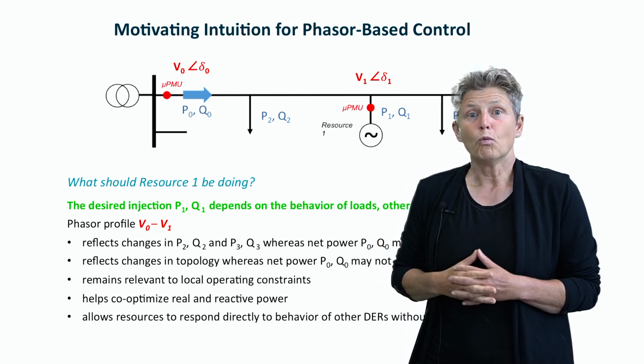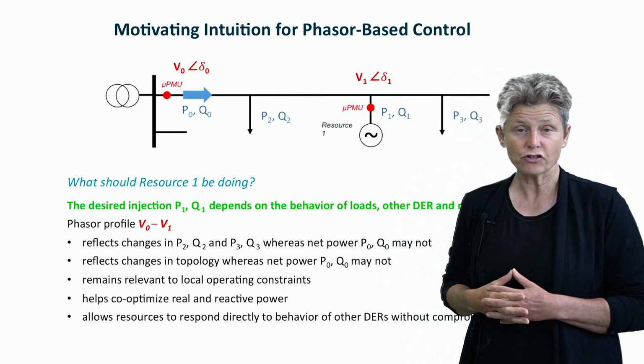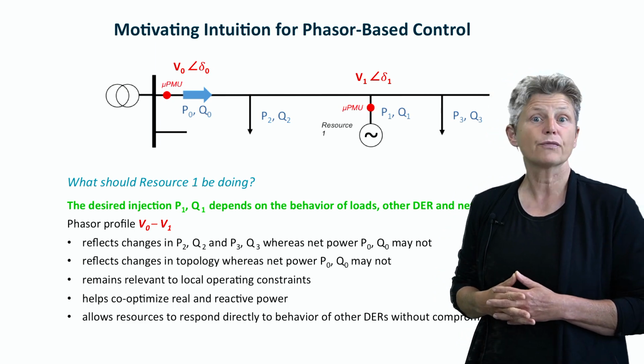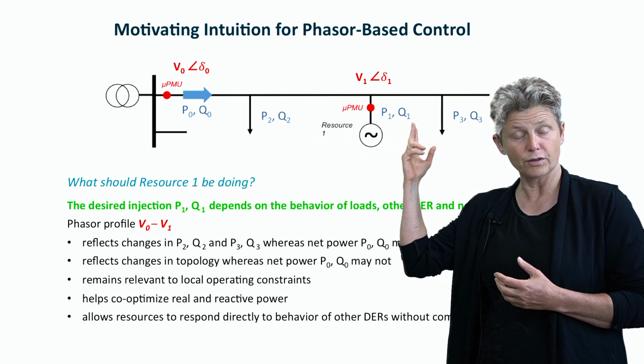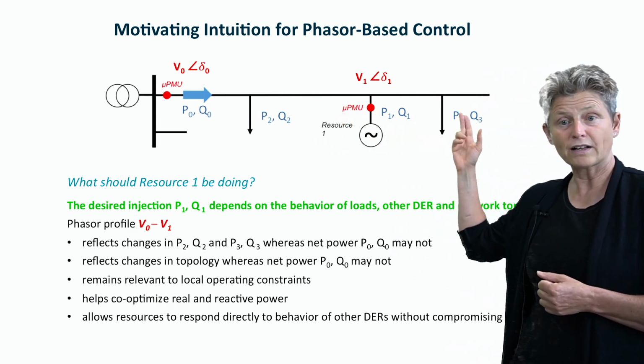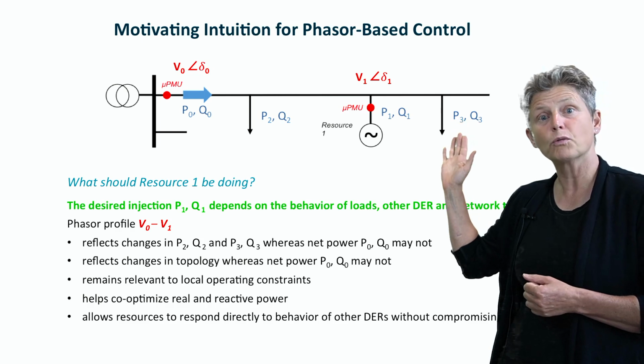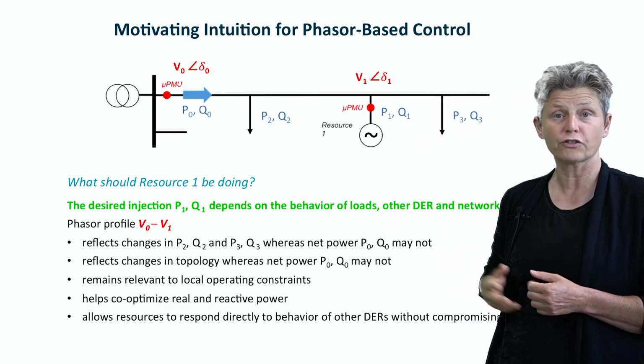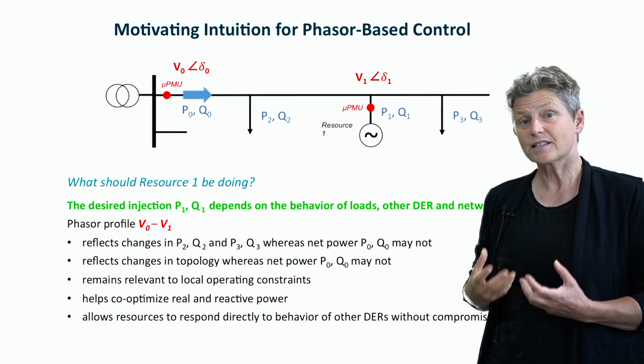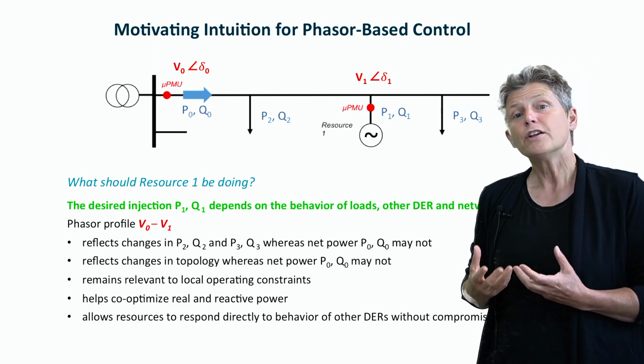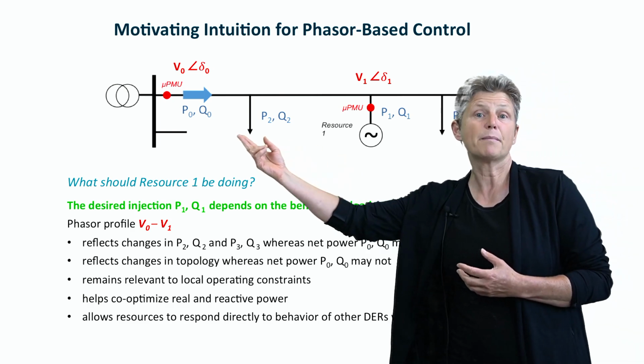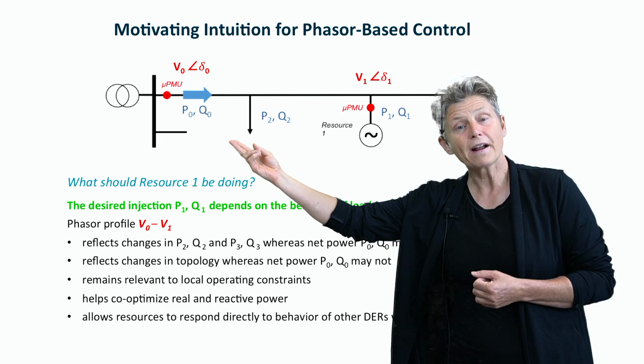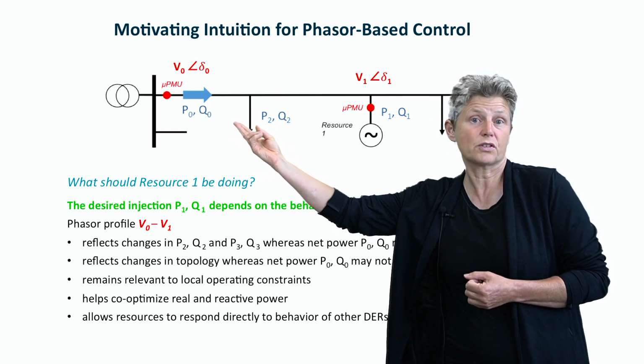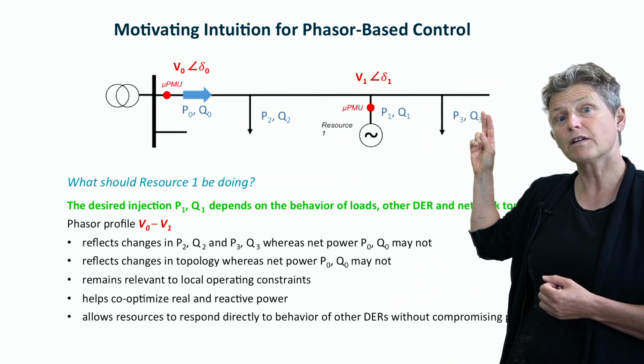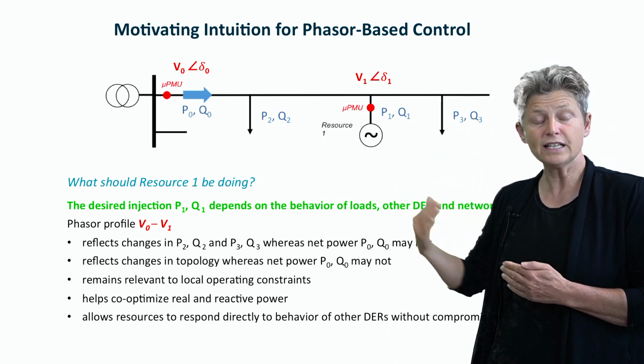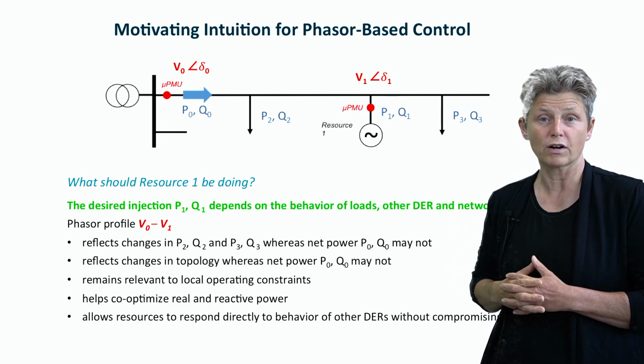That's doable. What you lose in doing so is the locational information, because if you're worried about the voltage profile along the circuit, which will drag the voltage down if there's too much load at the end, or push the voltage up too far if there's too much generation at the end, you will see that in the voltage phasor profile. You would lose that by measuring just P and Q. You wouldn't know where the extra load is happening. If it's close to the substation, maybe we don't care.